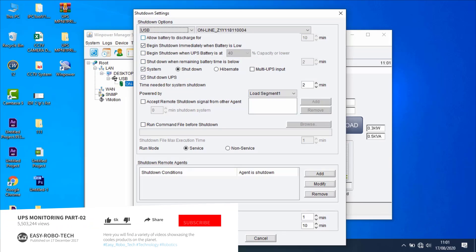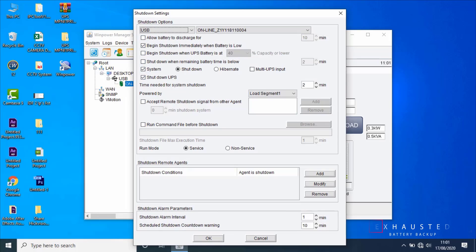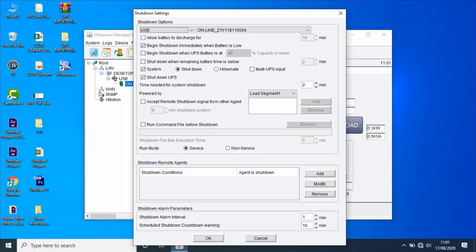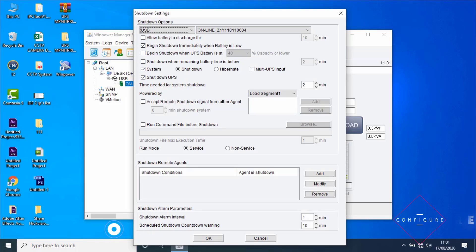Condition 1: when the battery backup time is exhausted after AC failure. Condition 2: when UPS battery is low. Condition 3: when UPS battery capacity is at the setting value or lower. Condition 4: when UPS battery remaining time is below the setting value. Condition 5: schedule shutdown of UPS output on a specific time or weekly. Conditions 1, 2, 3, and 4 should be configured here.